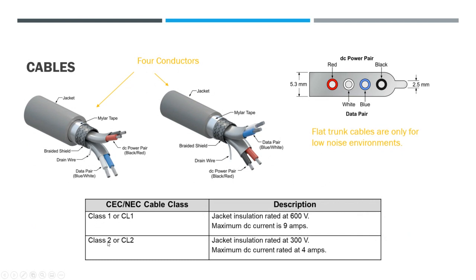And there are different classes, class one and class two. The major difference between class one and class two is the amount of load they can carry. Class one can carry up to 9 amps and 600 volts. Class two, 4 amps, 300 volts.